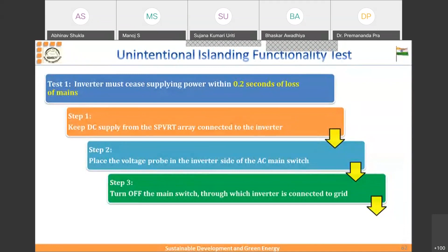This test must be conducted during noon time on a sunny day. What is the test? You go in front of the inverter and stop the supply within 0.2 seconds, it will shut down. The DC supply from the solar photovoltaic array stays connected, and you place the voltage probe on the inverter side at the AC mains - as you turn it off, everything will go down.